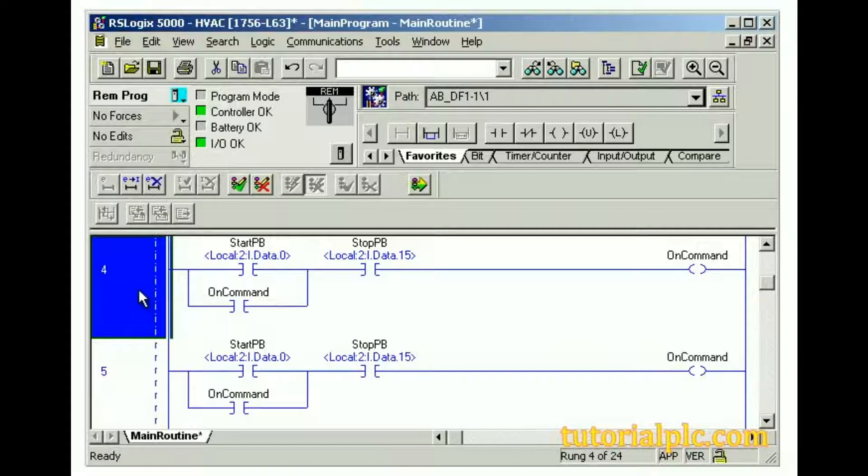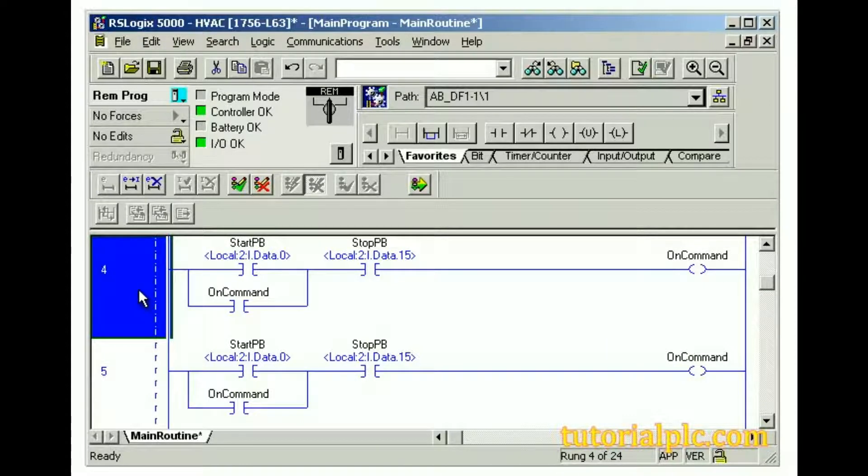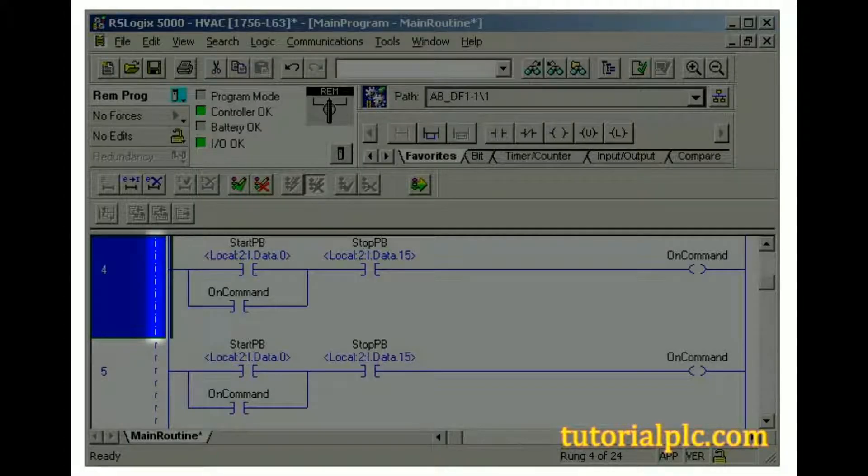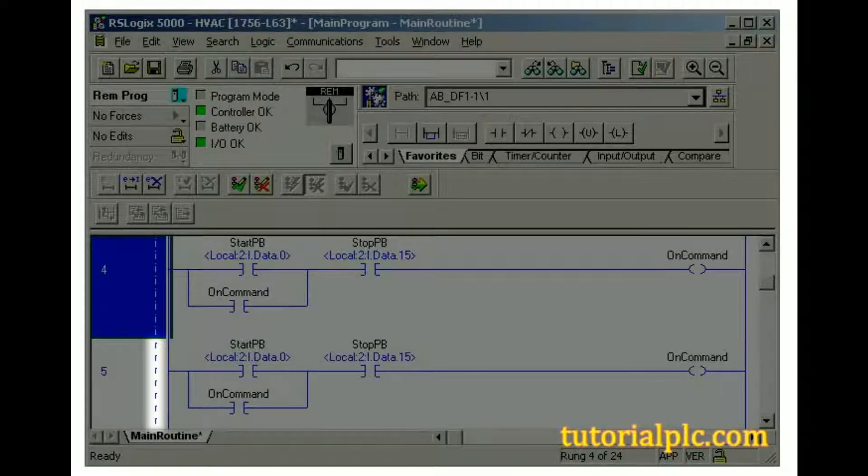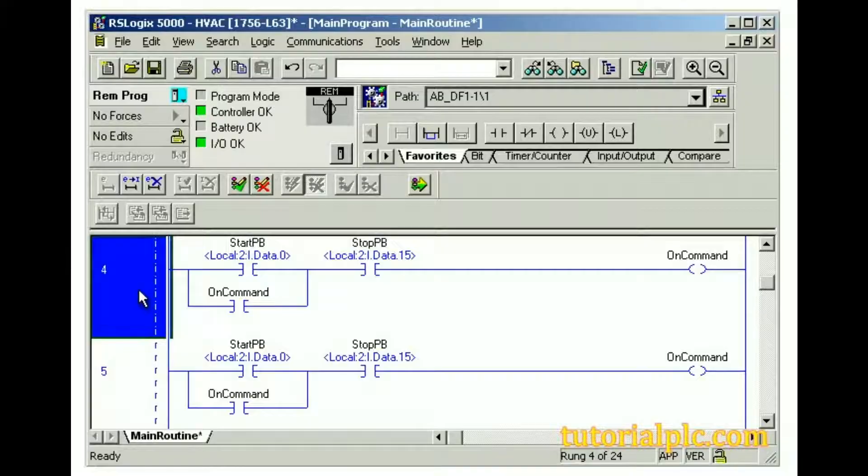A duplicate rung is displayed. Notice that rung numbers after the edit are temporarily changed while the edit rung is being modified. In the duplicate pair, the top rung is the rung being edited. The edit zone markers are lowercase i's. This indicates that the rung will be inserted. The bottom rung is the rung that is active in the controller. The edit zone markers are lowercase r's. This indicates that the rung will be replaced.